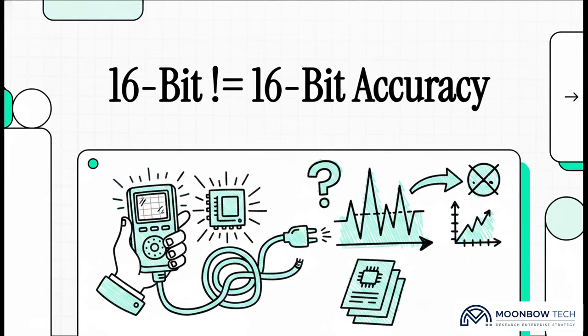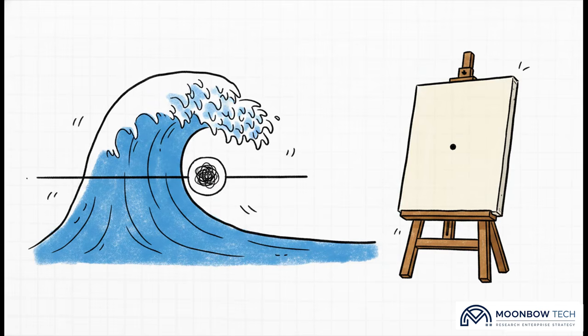Well, today we're going to look at exactly why a 16-bit meter can still give you a remarkably bad measurement. In university laboratories and power quality research, we constantly run into this massive practical tension. If you're monitoring a main feed, you absolutely need a measurement range large enough to avoid clipping the fundamental current and all those large, unpredictable transient peaks.